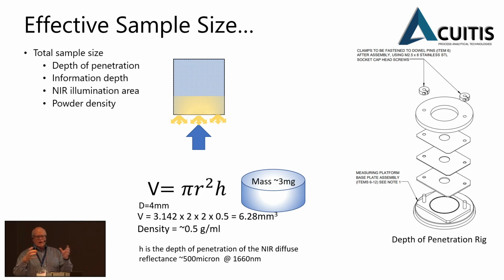The bigger the area you scan, the more sample you examine. And that's why the BU unit has a big window. Because these fiber optic probes have a fairly small window, about 5 millimeters across, the amount of material that actually contributes to a spectrum, if the powder is stationary in front of the probe, is only about 3 to 5 milligrams. And there's a real big problem with that. One is the non-homogeneity of the blends you're looking at, and the fact that we need to do measurements at a unit dose weight. And 3 milligrams is not a unit dose weight. There is no product that's sold with a weight of 3 milligrams. They're usually 300 milligrams. So that's one of the limitations of those fiber optic probes. They're very convenient, but they only see a tiny amount of powder.